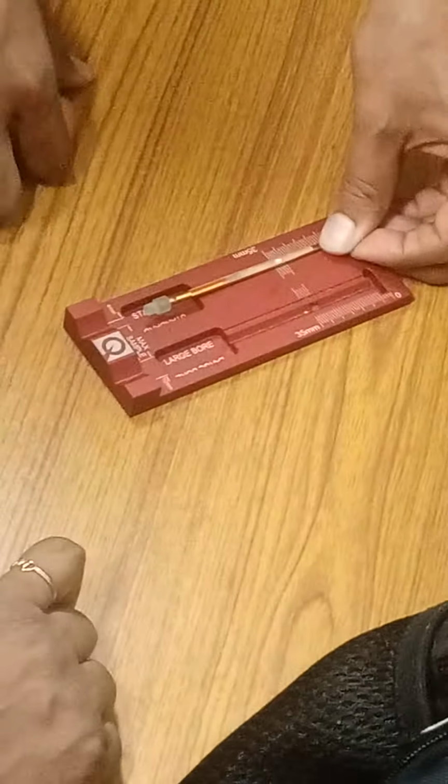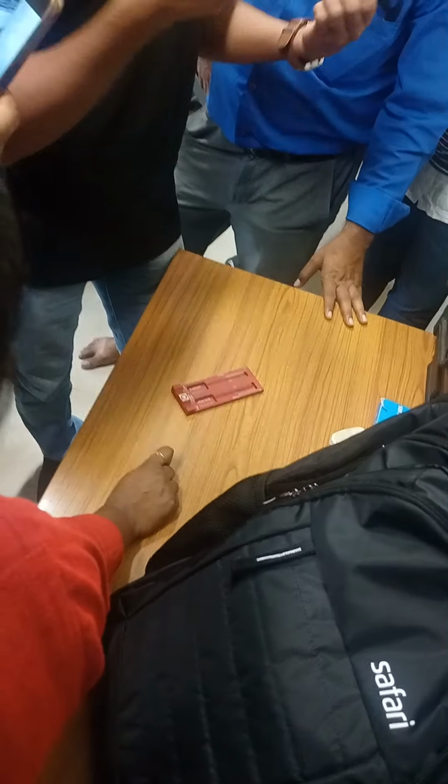The whole system will vibrate. The magnetic moment is created in this. If the sample vibrates, it means you packed it loosely, meaning these two Teflon caps are not tight.